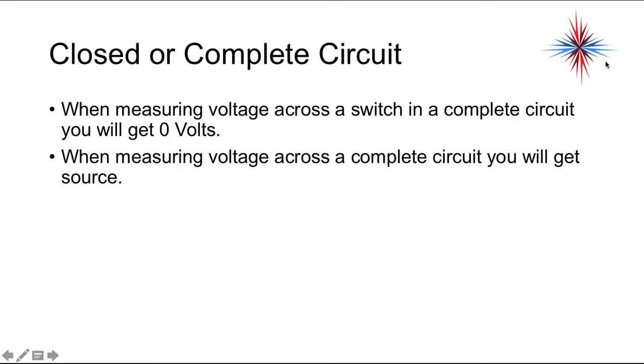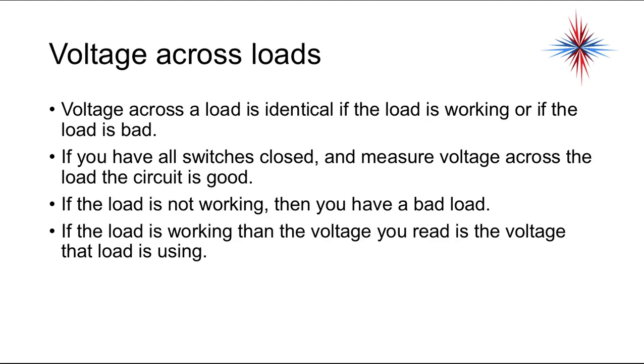When measuring voltage across a switch in a complete circuit, you will always get 0 volts because voltage across a closed switch is always 0. When measuring voltage across a complete circuit, you will get source. I'm going to add one more in here because we have voltage across loads. Voltage across a load is identical if the load is working or if the load is bad. If you have all the switches closed and measure voltage across the load, the circuit is good. If the load is not working, then you have a bad load. If the load is working, then the voltage you read is the voltage the load is using.